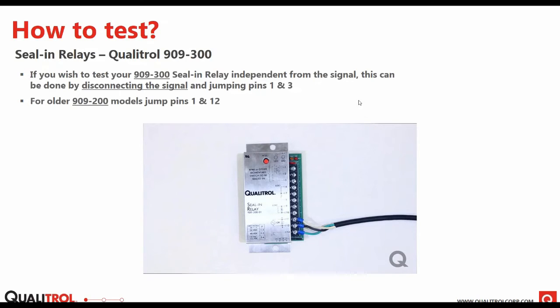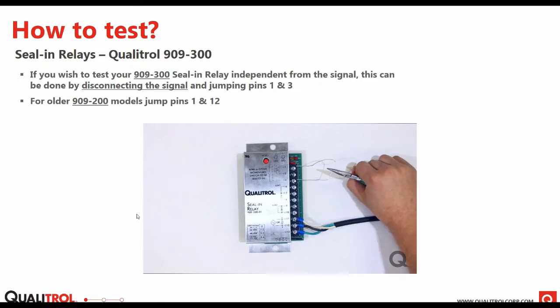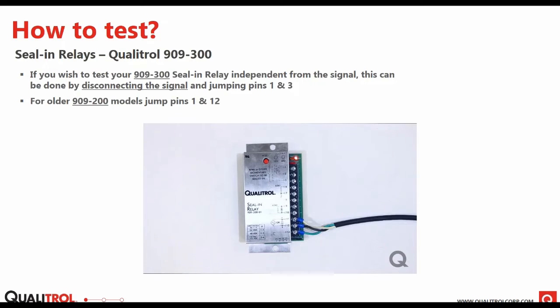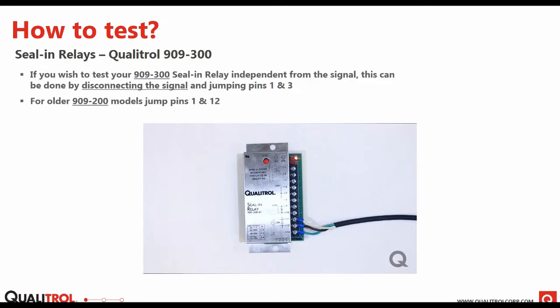We often get questions on how to test these and make sure that they're functioning properly in the field. That is also incredibly easy, similar to the past products that we've looked at. With the 909-300, which is the most current model we offer, the 909-200 is the previous model, which is now obsolete. Testing the 909-300 is very simple. What you're going to do is lift the signal from the input, which is pins 1, 2, and 3 on the 909-300. Say you have an RPRR hooked up to it, you want to disconnect that, and all you do is jump pins 1 and 3. This will simulate a contact closing on those terminals, which will give you your trip function.